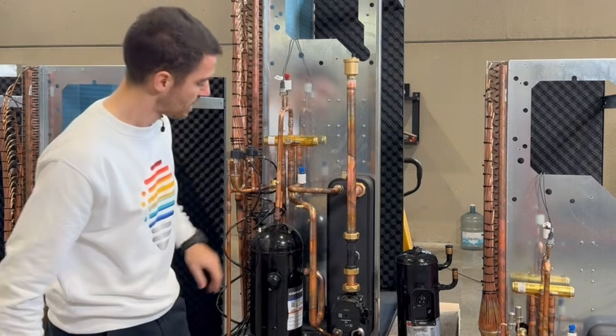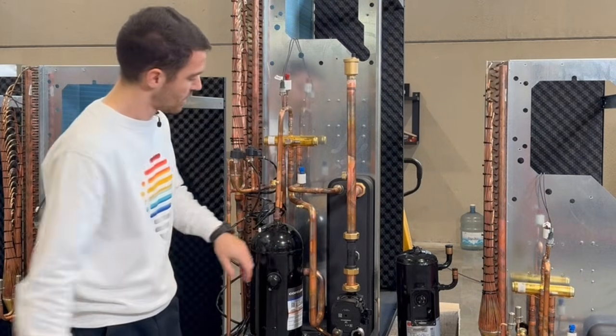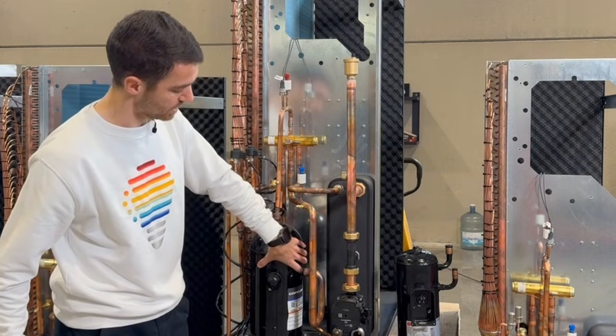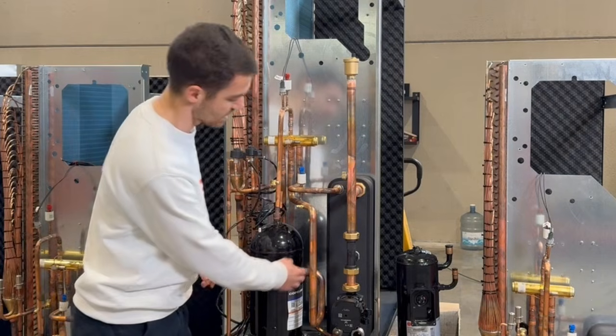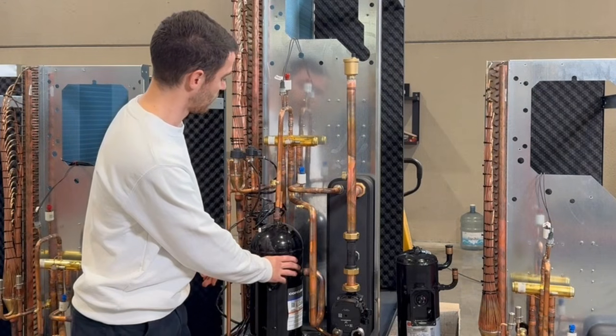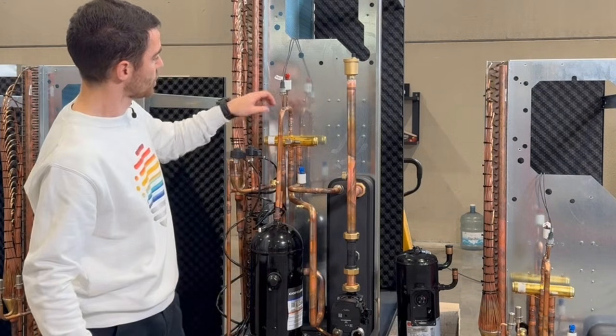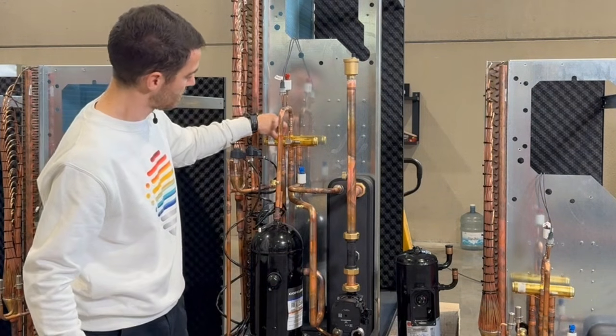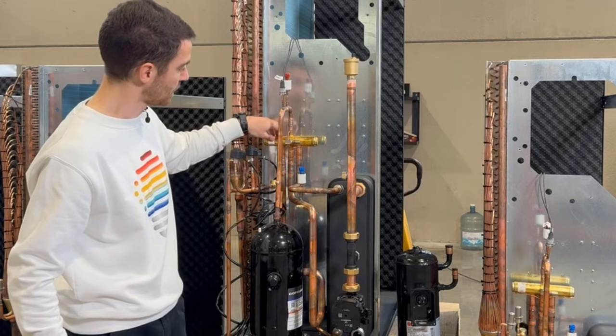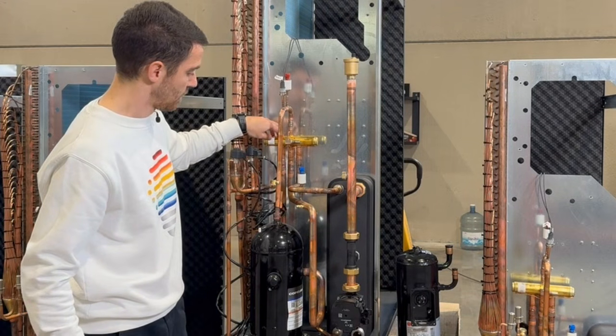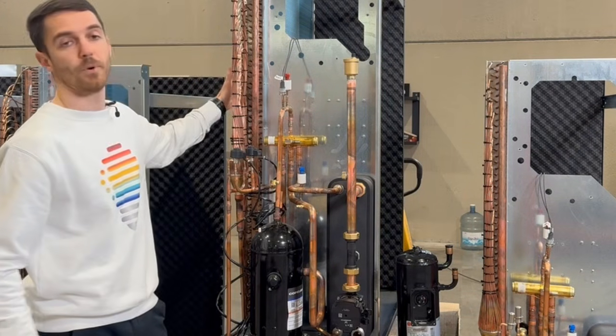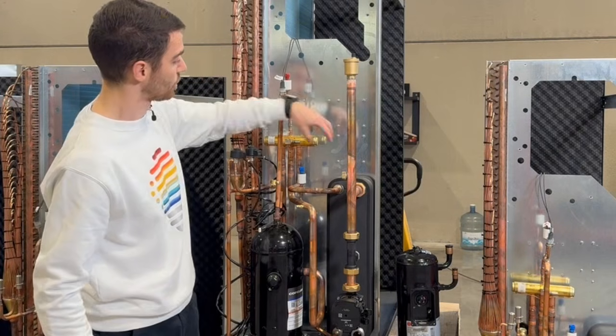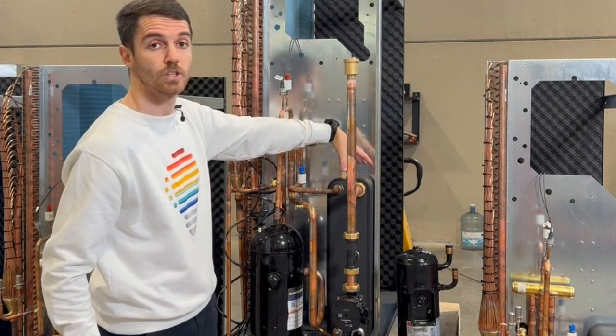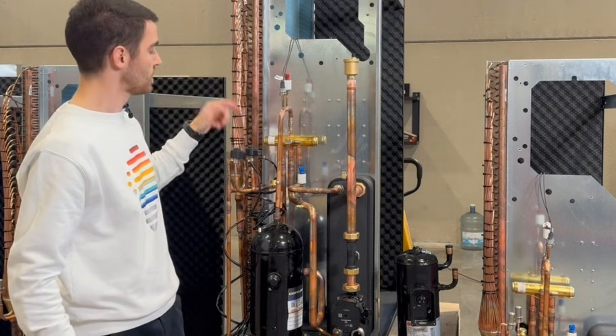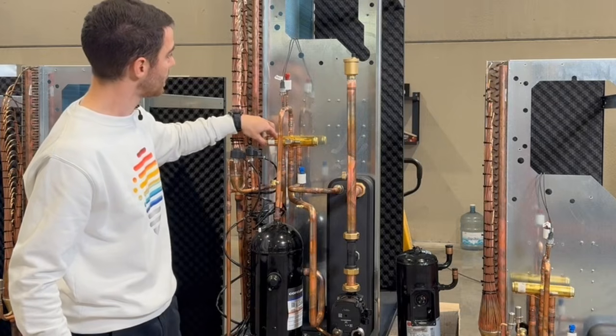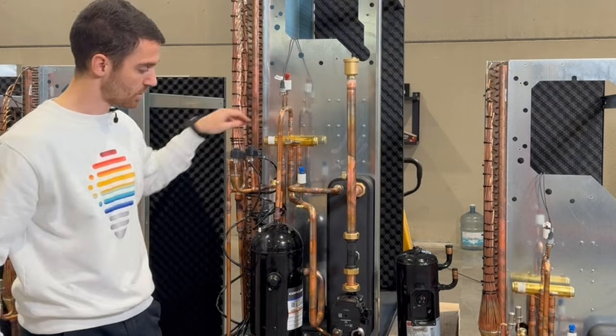From compressor, we have suction of compressor. So you can see here that this is scroll compressor because suction is going here. Discharge is going into 4-way valve and then is deciding if it's in heating or in cooling. It's going to evaporator to outdoor heat exchanger or condenser plate heat exchanger in heating. In cooling, it's opposite because 4-way valve is switching the circuits.